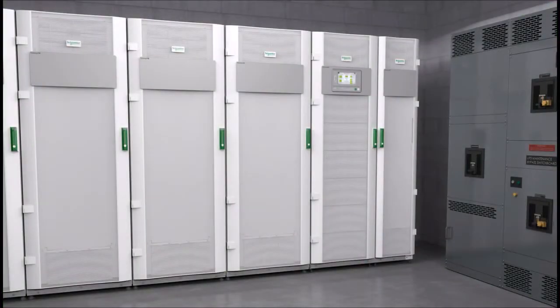Today, we are going to demonstrate how to configure the input contact and output relays on a Galaxy VM display. The input contacts can be configured for the UPS to control battery charging or give an alarm condition for specific functions. The output relays can be configured for the UPS to activate a relay to communicate to an external monitoring system when there is an alarm condition.